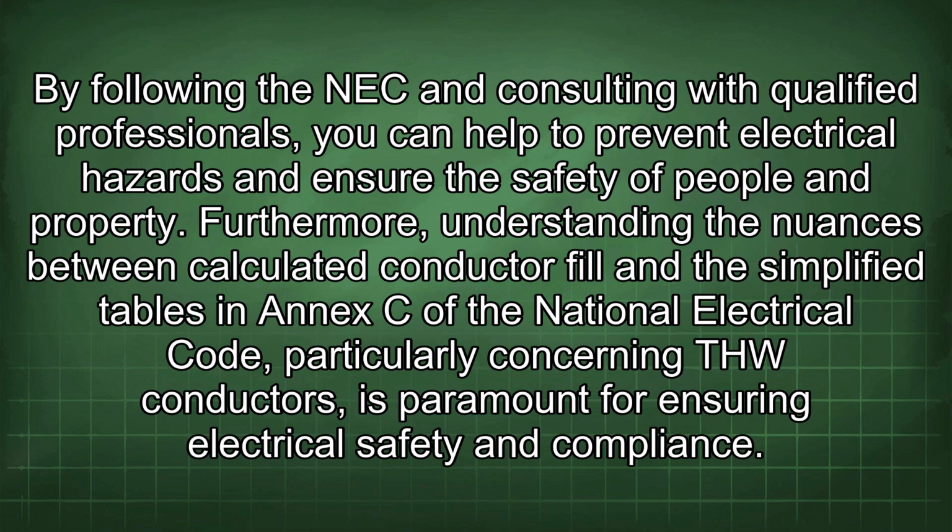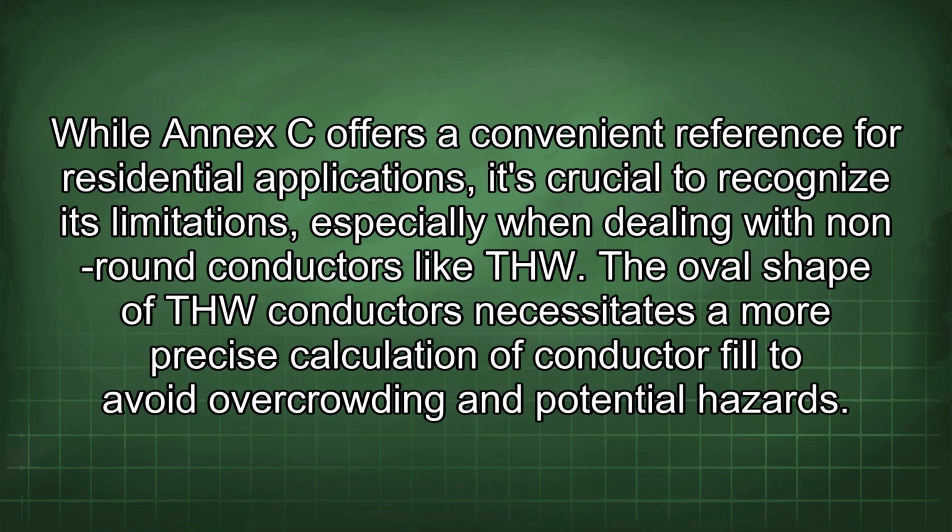of people and property. Furthermore, understanding the nuances between calculated conductor fill and the simplified tables in Annex C of the National Electrical Code, particularly concerning THW conductors, is paramount for ensuring electrical safety and compliance. While Annex C offers a convenient reference for residential applications, it's crucial to recognize its limitations, especially when dealing with non-round conductors like THW.